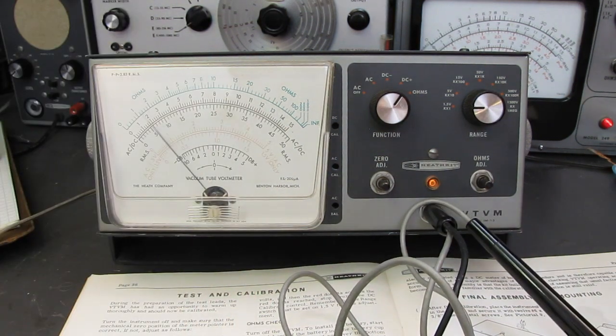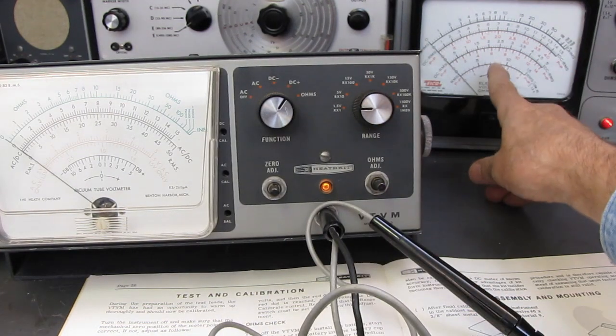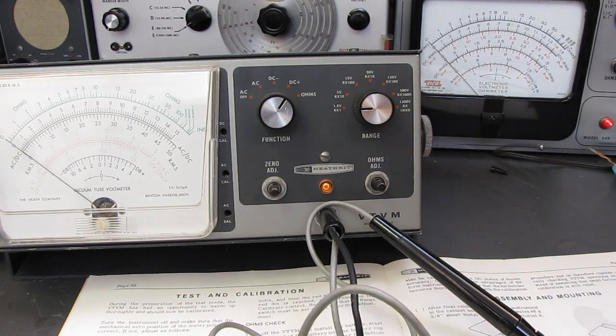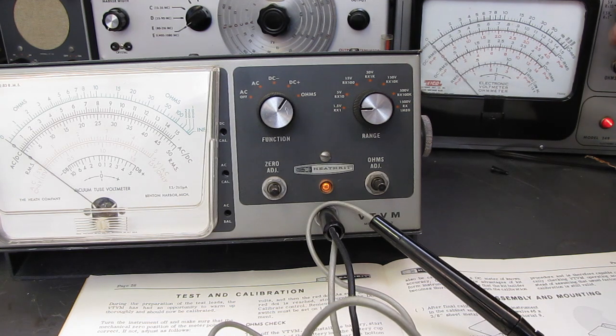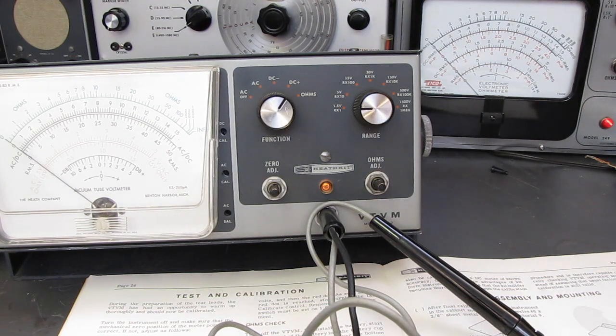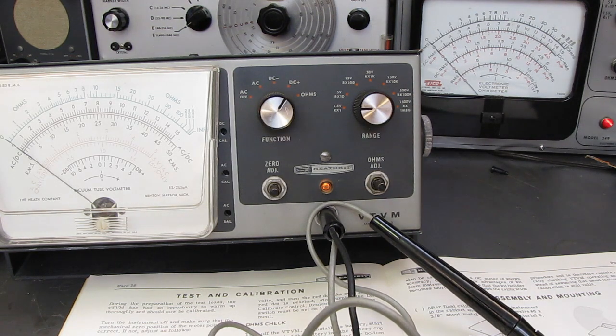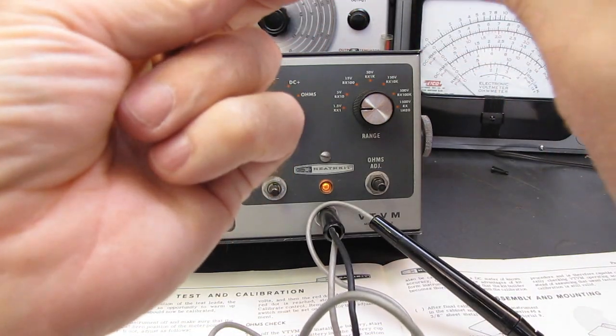Set the range switch to 1.5. It's 1.5. And the probe to DC. Now, on your VTVM probes, you're going to have a DC position and an AC ohms position. So we'll set it to the DC position. Connect to a flashlight battery. Adjust the DC calibrate so the meter pointer falls directly over the small red dot. Now, that was for carbon zinc batteries back in the day.